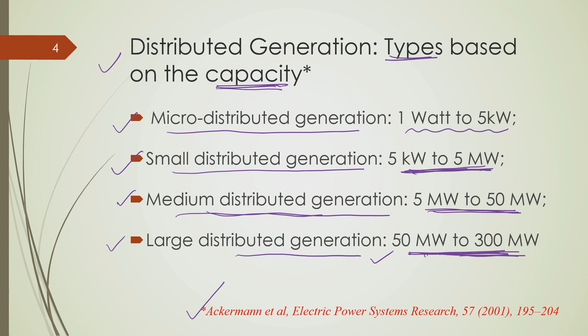According to this definition, as in the example I gave you, a typical industrial customer can be directly connected to a higher voltage, because 50 megawatt to 300 megawatt is a very high value to integrate in a typical 11 kV primary distribution network. It is not feasible. So, one needs to connect this to a higher voltage distribution network, which may be 110 kV or 132 kV, which we often categorize as the sub transmission system. So, if an industrial customer is directly connected to a sub transmission network at 110 or 132 kV voltage level, one can connect large distributed generation as explained.